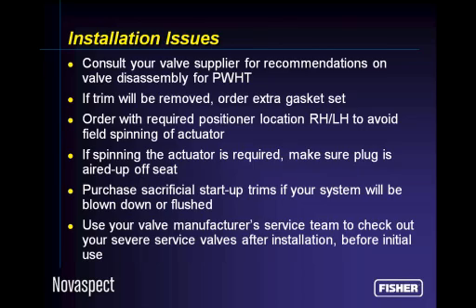Do not, if we made a mistake and did not pay attention to the fact that your valve was mounted up against a wall, and you've got a positioner, let's say, mounted on the valve actuator, it's now up against the wall. And your instrument mechanics are going to read you the riot act because they can't get behind there, they can't get the cover off, they can't do a valve calibration. So make sure that you tell your valve supplier what side of the valve, in relation to which direction the valve is flowing, you would like the positioner on.